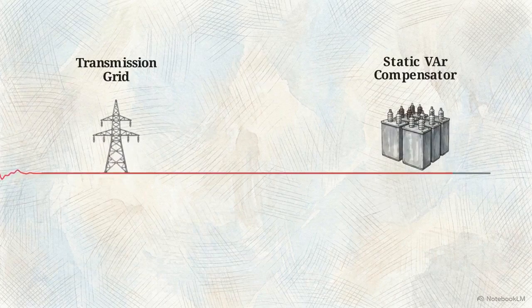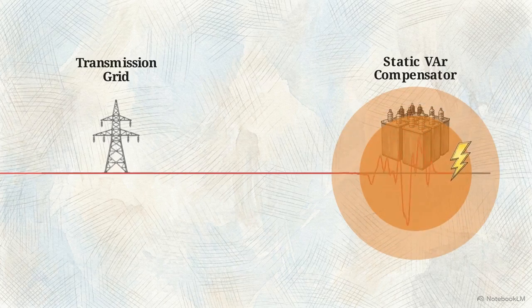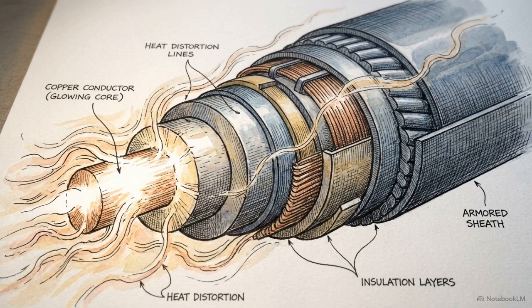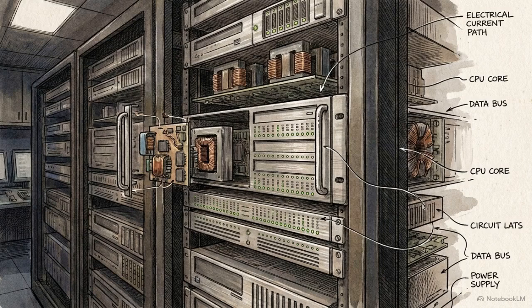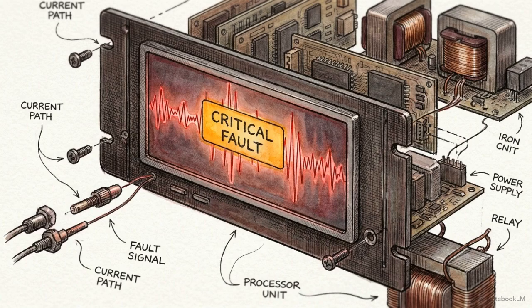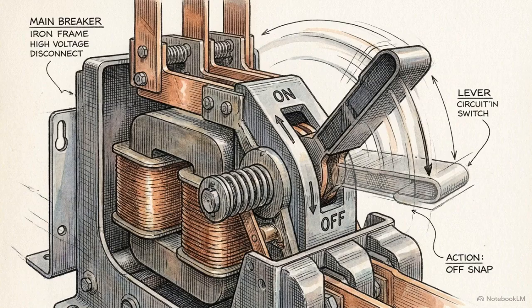The harmonic currents hit the capacitor branches of the SVCs first. Because capacitors have naturally low impedance to these specific high-frequency harmonics, the currents were magnified. This created a resonant condition that pushed the electrical flow far beyond normal limits. Monitoring these systems are protective relays, automated computers programmed to detect standard faults, like short circuits or overloaded lines. The relays identified the harmonic resonance as a terminal equipment failure. Following their programmed logic, they triggered an immediate automatic system shutdown to protect the SVCs from physical damage. In doing so, the automated safety systems disconnected the very equipment required to prevent a total voltage collapse.